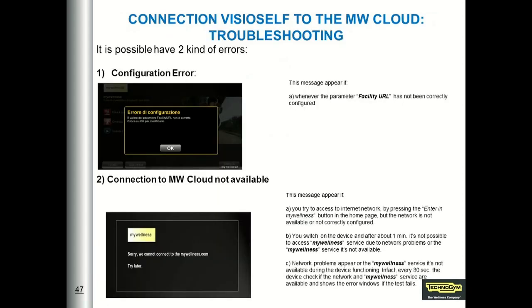What can go wrong with the VisioSelf? For example, if the facility URL we insert is not available — for instance, if we spell the name wrongly — the VisioSelf checks with the service whether there is a facility URL corresponding to the name, and if it cannot find any, it will return an error message. In this case, we have to correct the facility URL. The other type of error shown here occurs when the VisioSelf cannot connect to the internet and so cannot reach the facility we have entered.